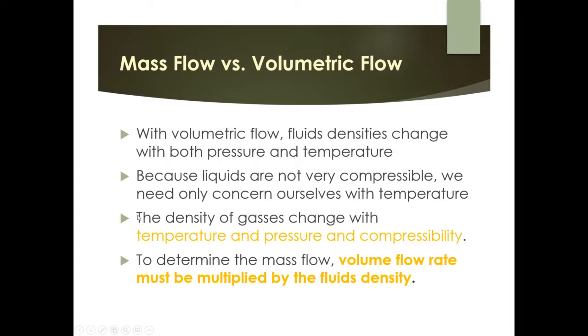To determine mass flow, take the volumetric flow rate and multiply it by the fluid's density. That density component is the only big difference between mass flow and volumetric flow. Depending on the medium, density is affected by at least temperature, and possibly also by pressure and compressibility.